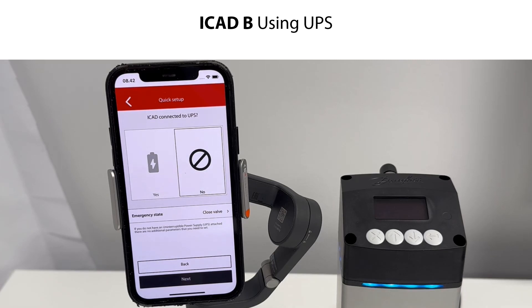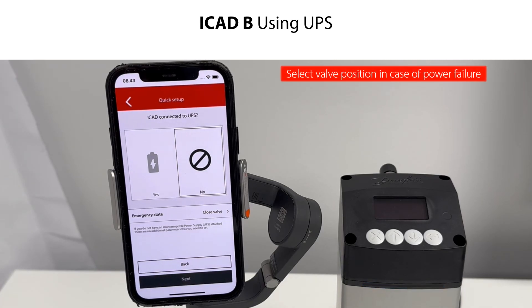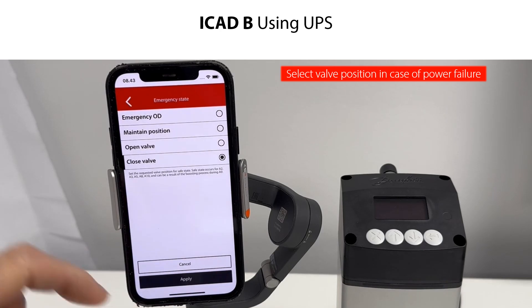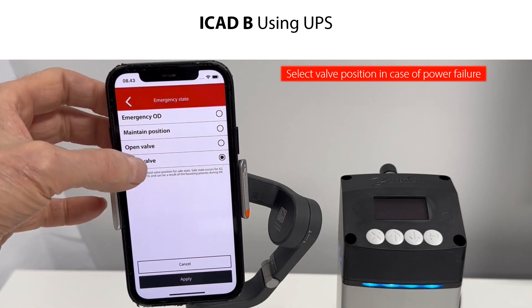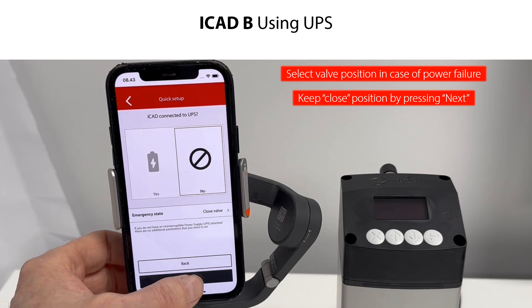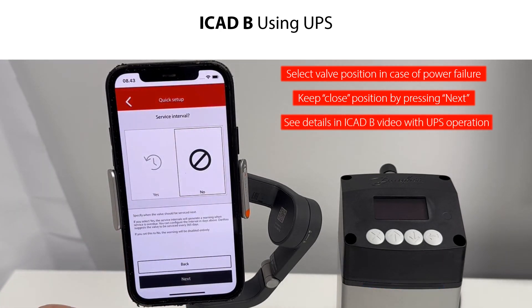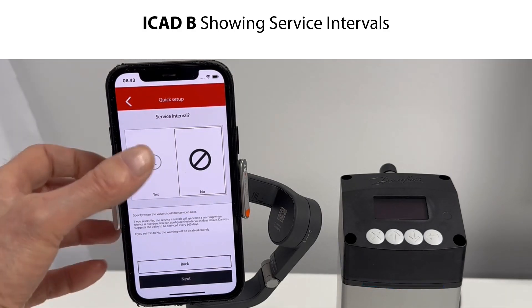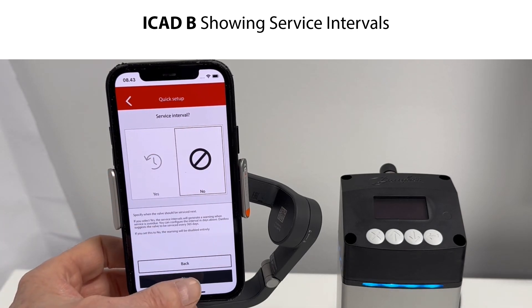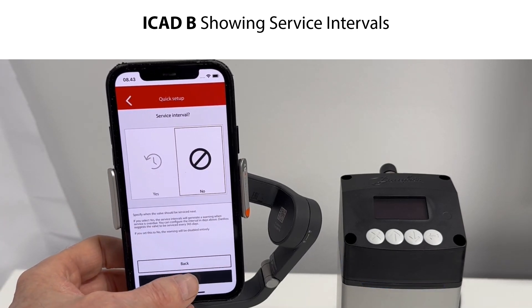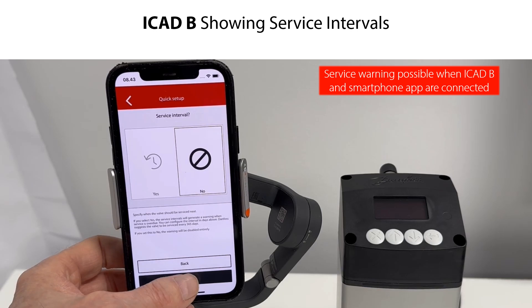You also need to specify how the valve position should be in emergency state in case of a power failure. The default valve position is closed, so in this example we keep this and confirm by pressing Next. Please see more details about emergency state in a separate ICAD-B setup and configuration video. Finally, you are asked to specify the valve service intervals so that you get a warning in the ICAD-B smartphone app. The default answer is No, so in this example we keep this by pressing Next.